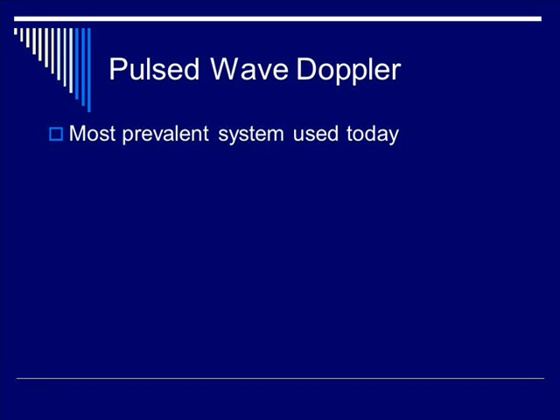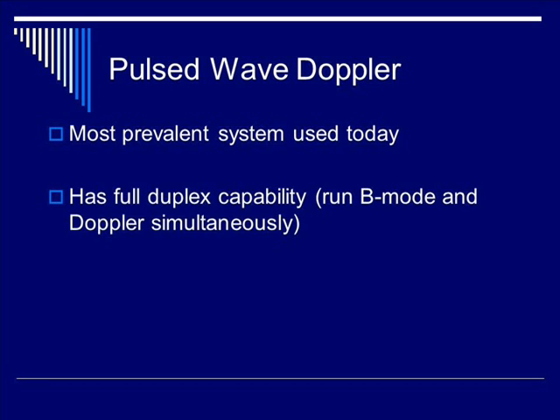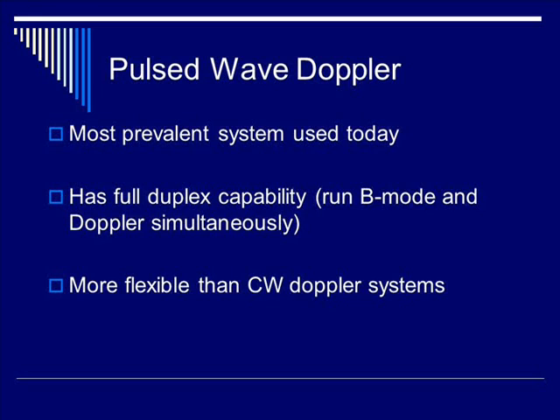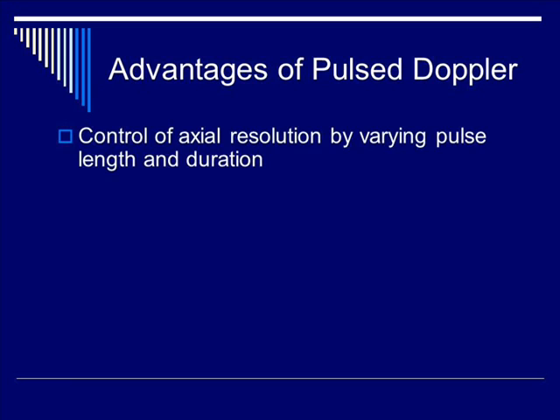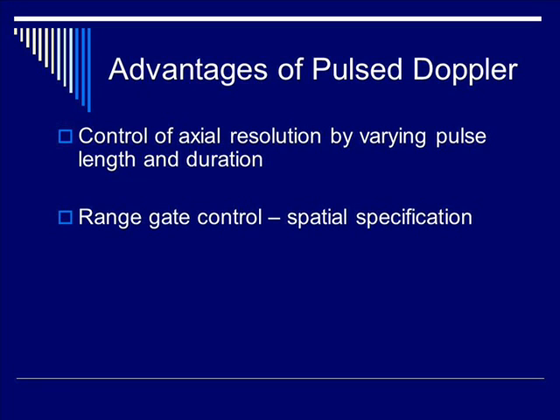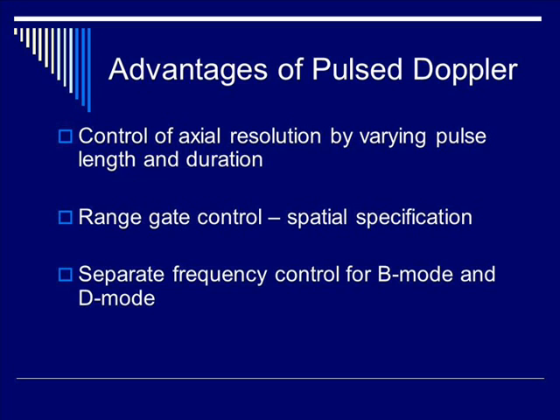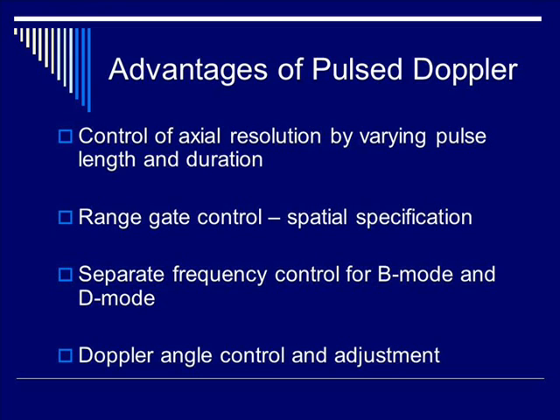Now let's talk about Pulse Wave Doppler. It is the most prevalent system used today. It has full duplex capability, meaning it can run B mode and Doppler simultaneously. It's more flexible than continuous wave Doppler systems. Advantages include: you can control axial resolution by varying pulse length and duration, control the gate range and specify the spatial volume, separate frequency control for both B mode and D mode, and the Doppler angle can be adjusted, allowing you to operate power Doppler versus regular Doppler.